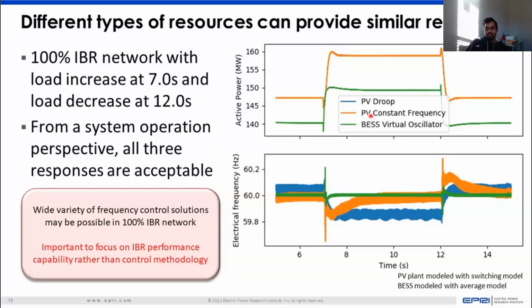Constant frequency control is what I showed in the previous slide, with distributed slack bus-based response. Droop curve is what we presently have in grid-based systems today. Virtual oscillator is a new form of inverter-based control that is coming up, providing a different kind of response. But from a system operator perspective, all three responses are acceptable.